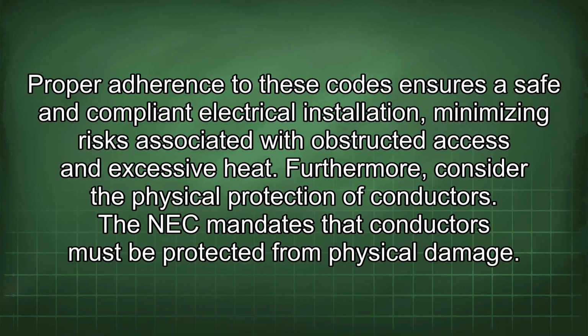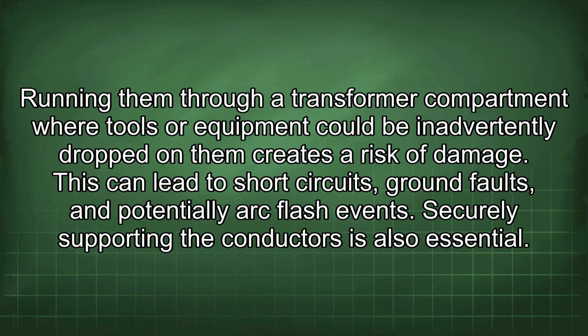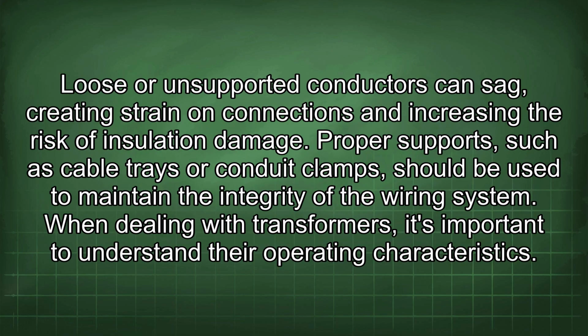Furthermore, consider the physical protection of conductors. The NEC mandates that conductors must be protected from physical damage. Running them through a transformer compartment where tools or equipment could be inadvertently dropped on them creates a risk of damage. This can lead to short circuits, ground faults, and potentially arc flash events. Securely supporting the conductors is also essential. Loose or unsupported conductors can sag, creating strain on connections and increasing the risk of insulation damage. Proper supports, such as cable trays or conduit clamps, should be used to maintain the integrity of the wiring system.